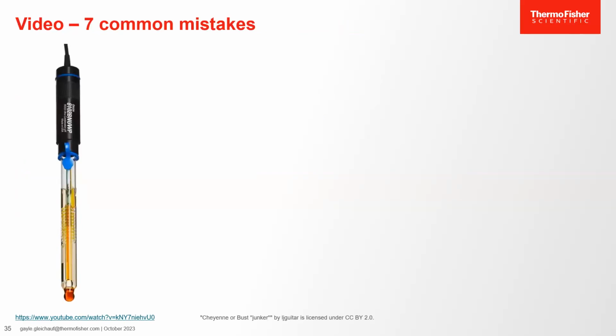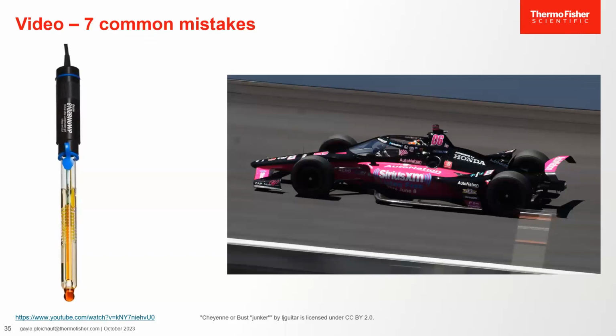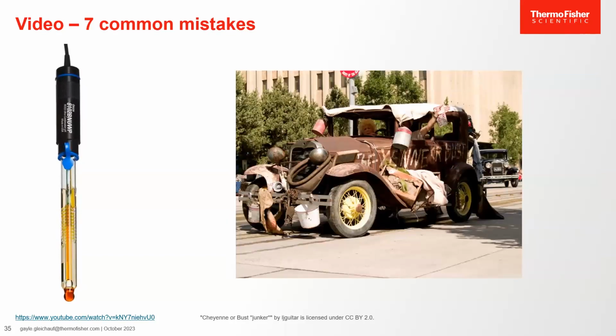pH is a very simple measurement until it's not. Age, neglect, and contamination can ruin the performance of a pH measurement system. A pH electrode is actually a precisely designed scientific instrument. Depending on how we handle and maintain our electrode, it can perform like a well-tuned race car or a junker. So pH electrodes require specific care, maintenance, and handling to properly perform.